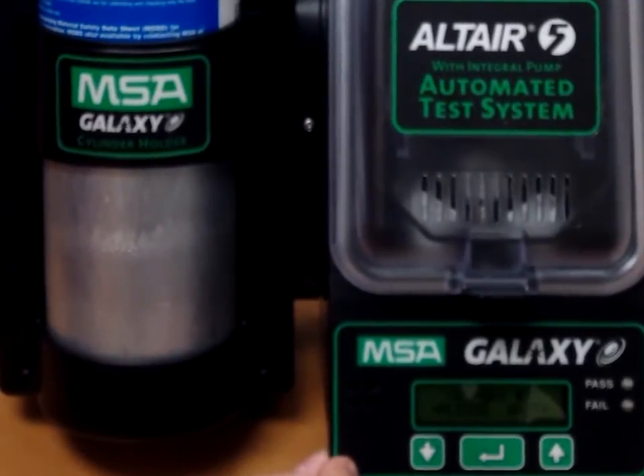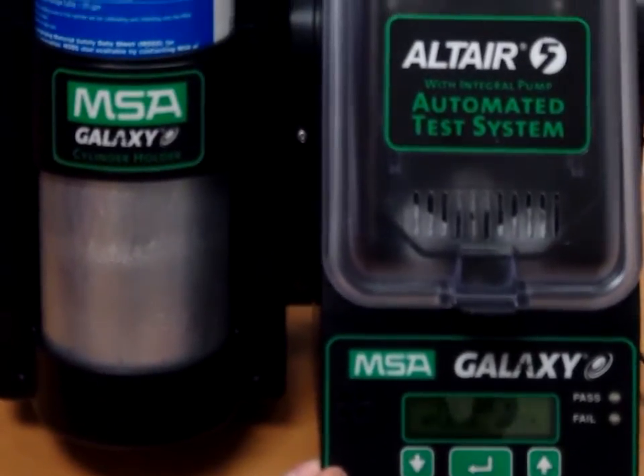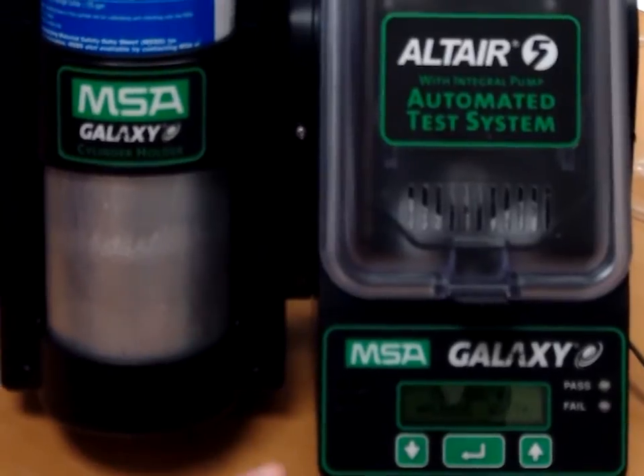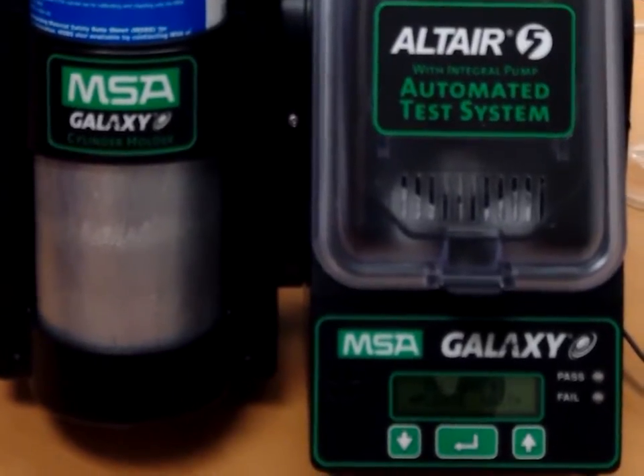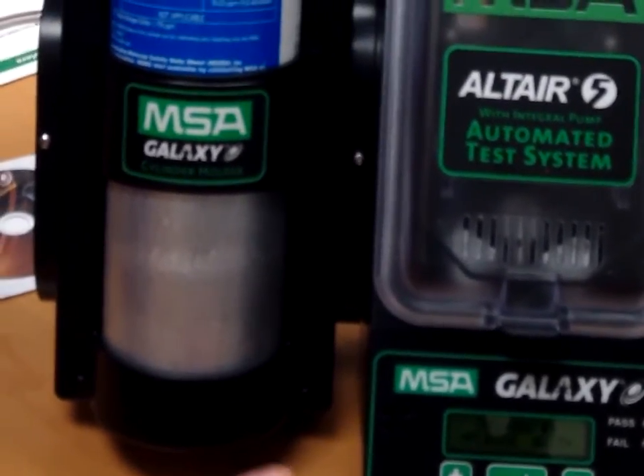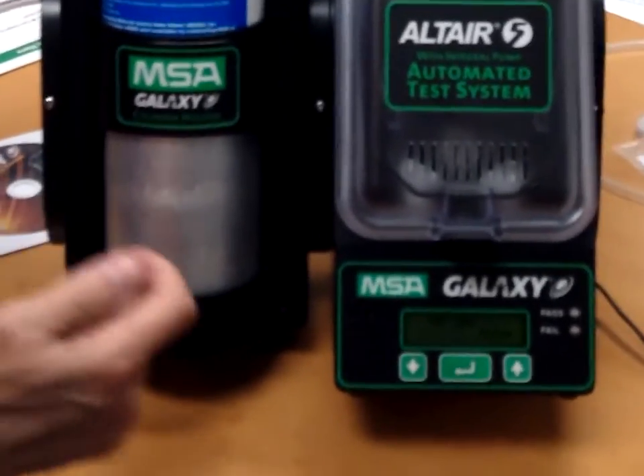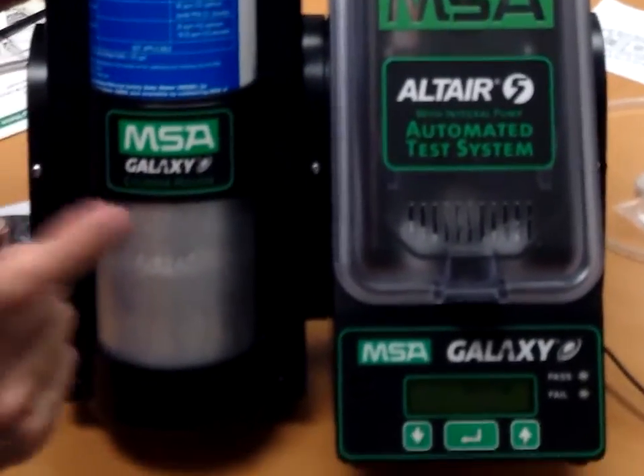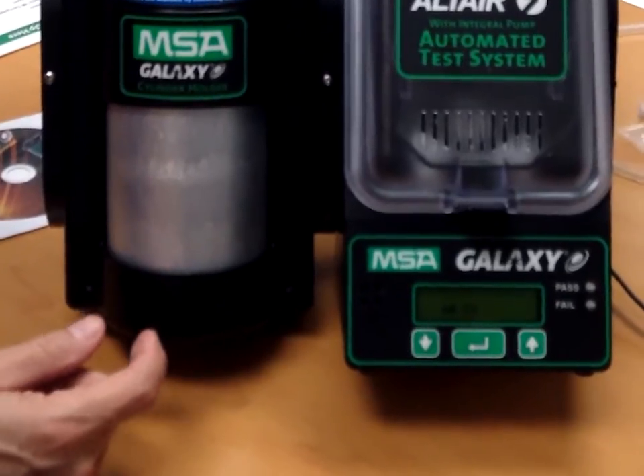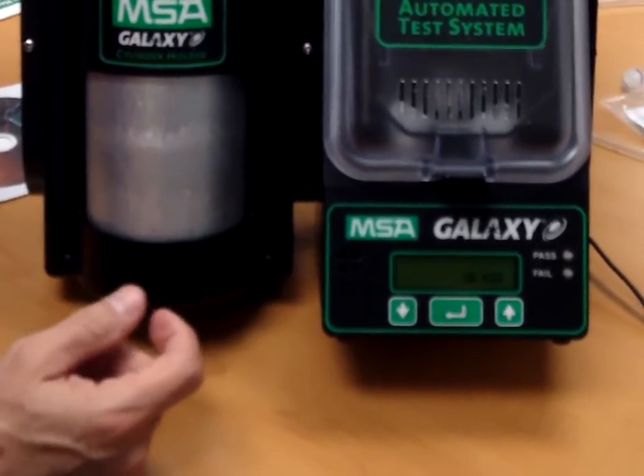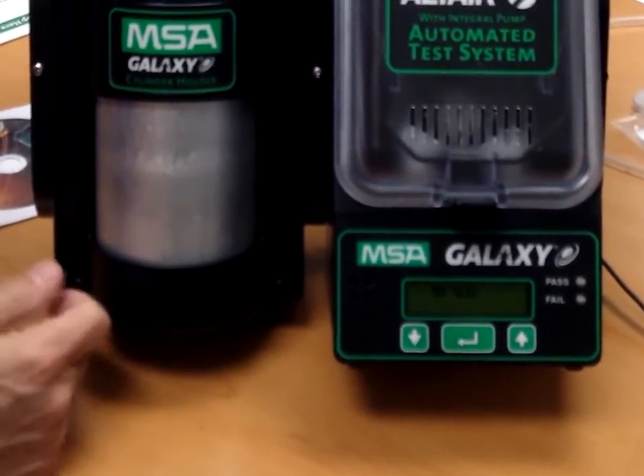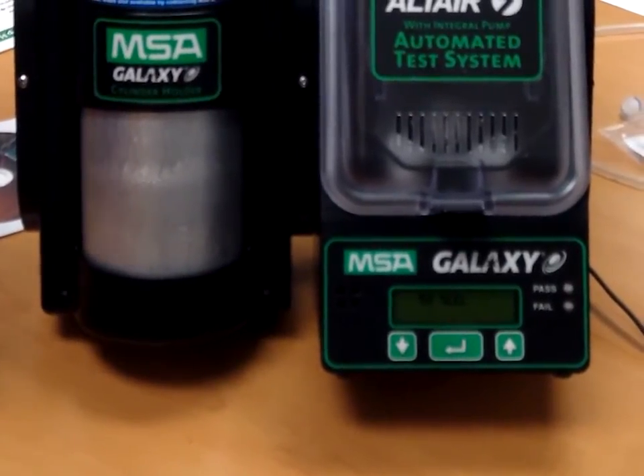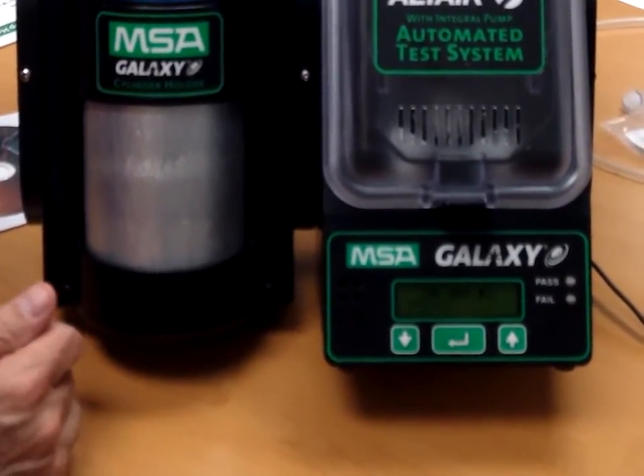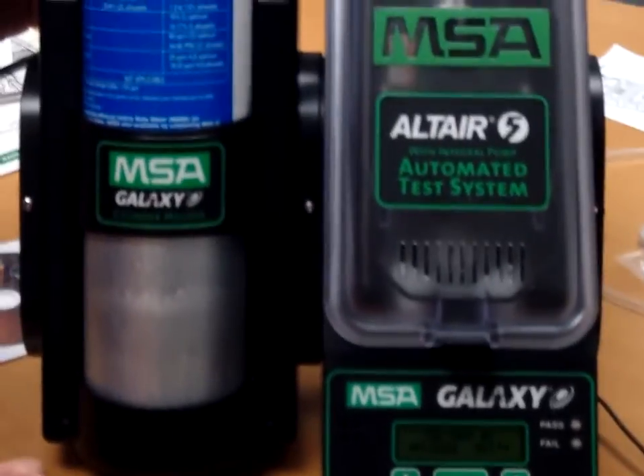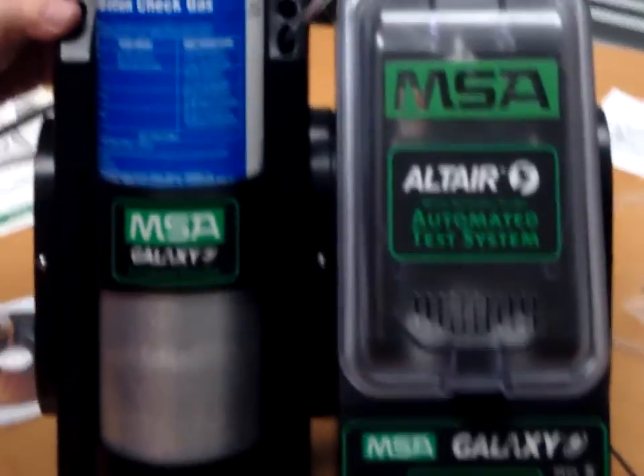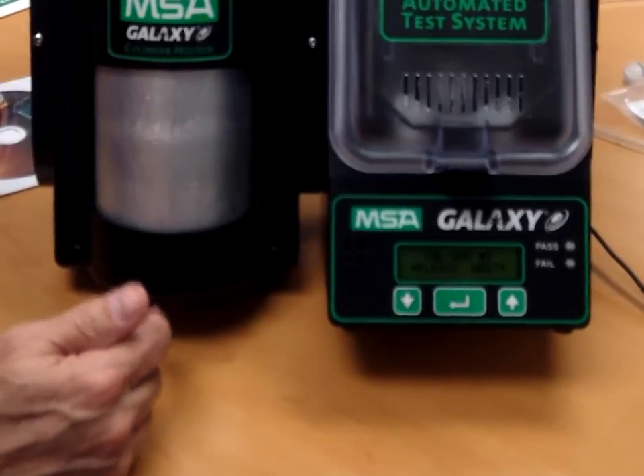So what are some typical reasons you may fail a calibration test? Good question. One reason you might fail is if you've got a sensor that might be going bad, and if that happens, when you go to turn on the unit, that sensor and that number will be flashing, letting you know that that particular sensor is in trouble. If you do have a sensor problem, you want to contact the supplier. You guys will be providing that information, and they can provide the replacement. Remember that the sensors are under warranty for 3 years, so if a sensor does go bad, you can replace it in the field.